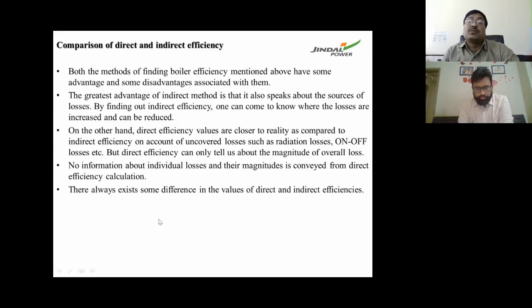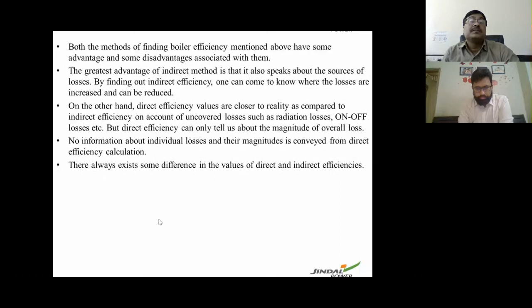So the direct efficiency gives you the figure for the uncovered losses, such as radiation losses and on-off losses like startup and shutdown losses. But direct efficiency can only tell us the magnitude of overall loss. No information about individual losses and their magnitude is conveyed from direct efficiency calculations. There are always differences between direct and indirect efficiencies.